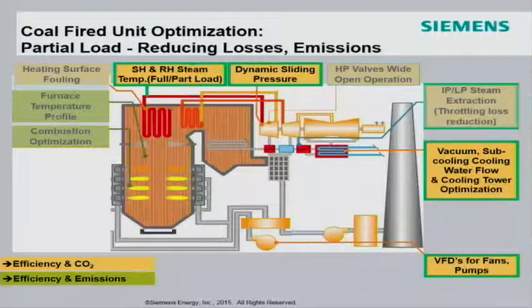The important point here, as all of you from power plants know, is that when you're firing at minimum load, it is not going to be balanced simply because of the burner configurations that you have when you go down low. You can have a really well-balanced fire, centered fireball in T-fired units, at maximum load. But once you start going down to lower loads, all of a sudden the availability of the burners you can use for the configuration makes the combustion a little bit imbalanced. And that's where these furnace measurements can actually get you back as balanced as possible.